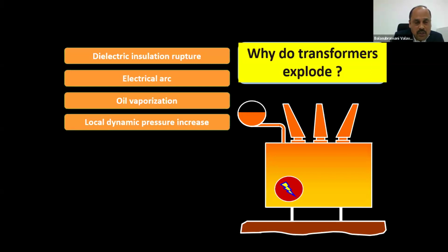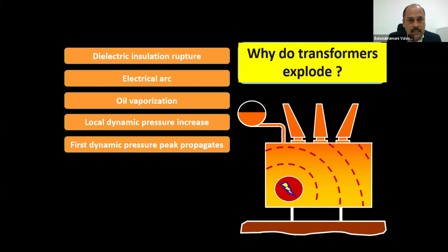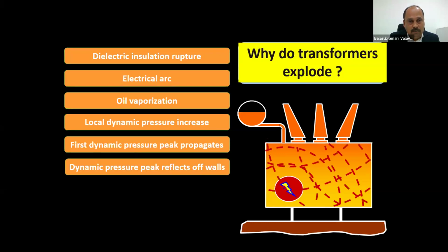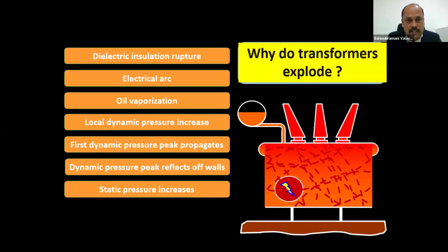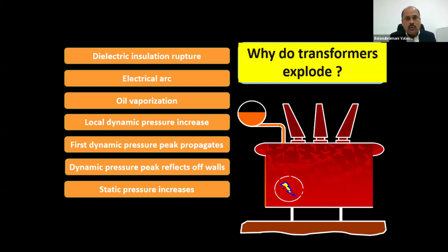The dynamic pressure travels very fast. Suppose, as shown here, it reaches within a few milliseconds. So the dynamic pressure is also converted into static pressure. When there is a high static pressure and you don't have the SERGI system, what happens? Because of fast propagation, static pressure increases and it tends to explode the tank, the complete transformer.